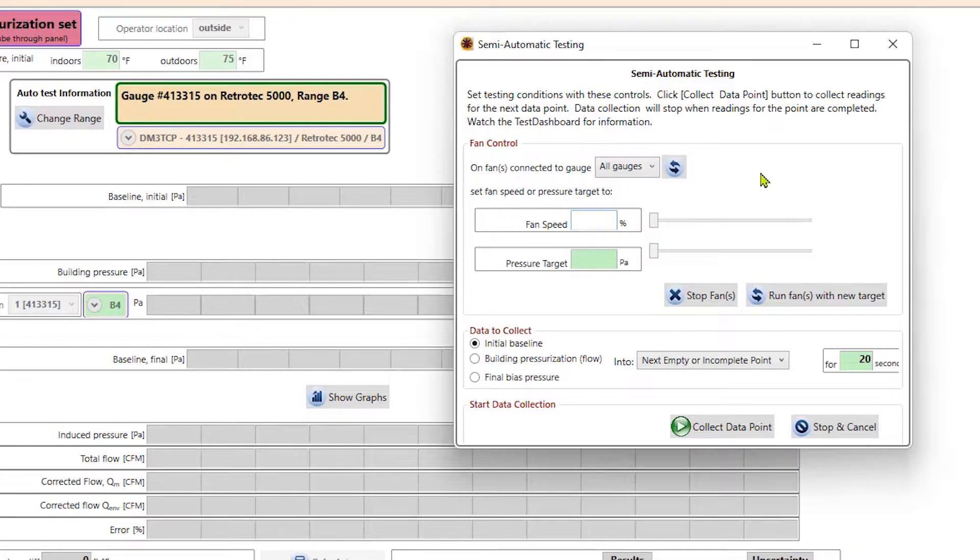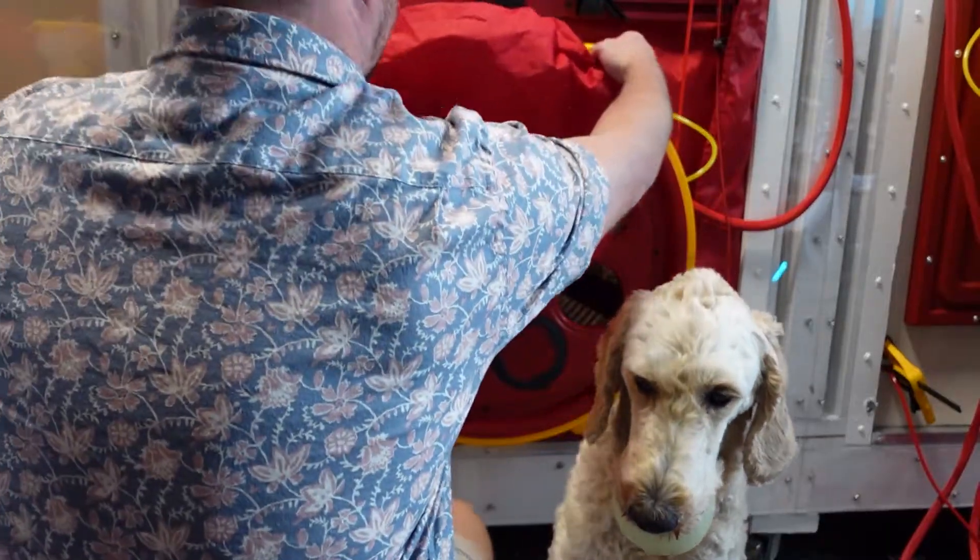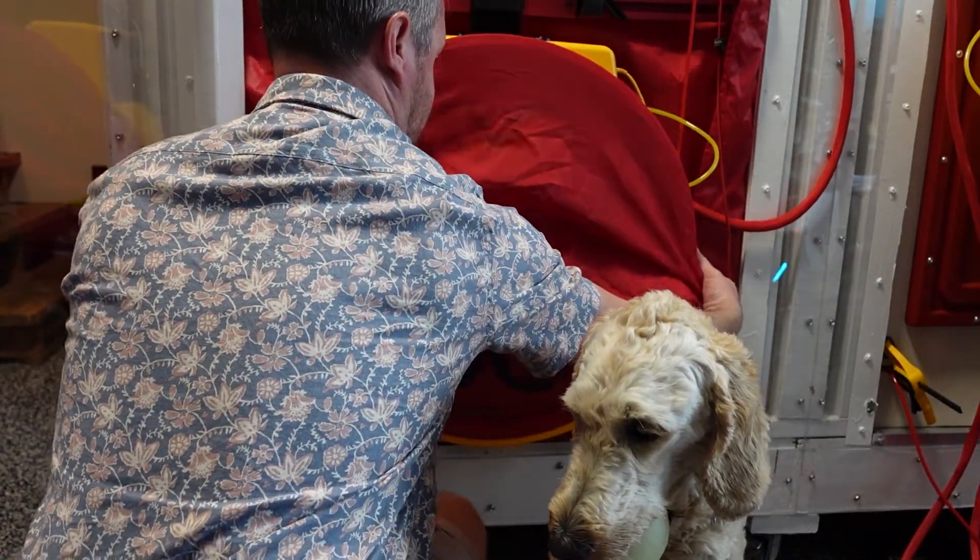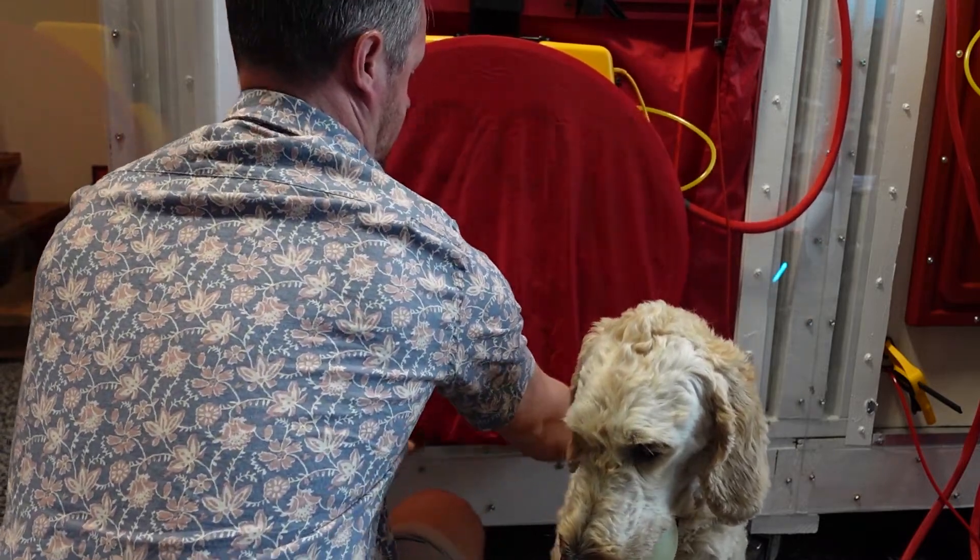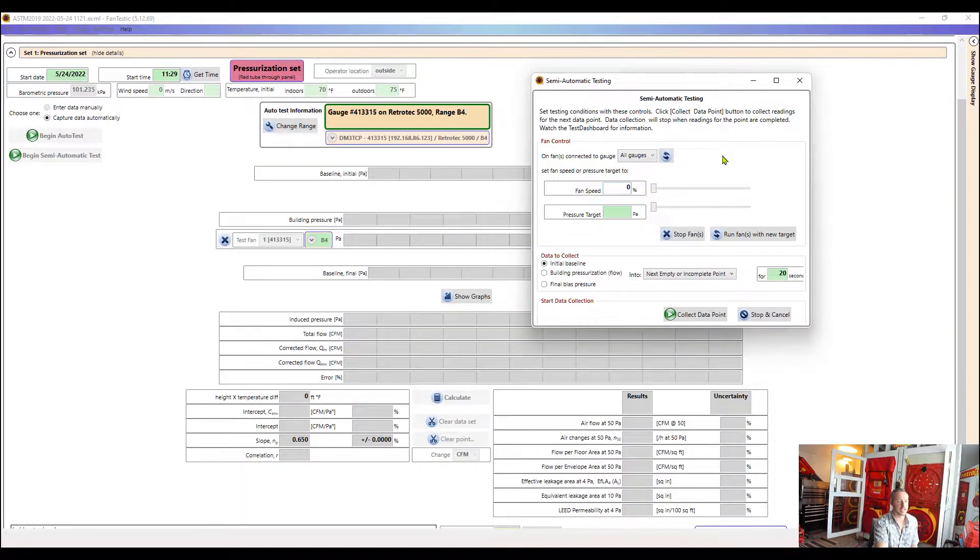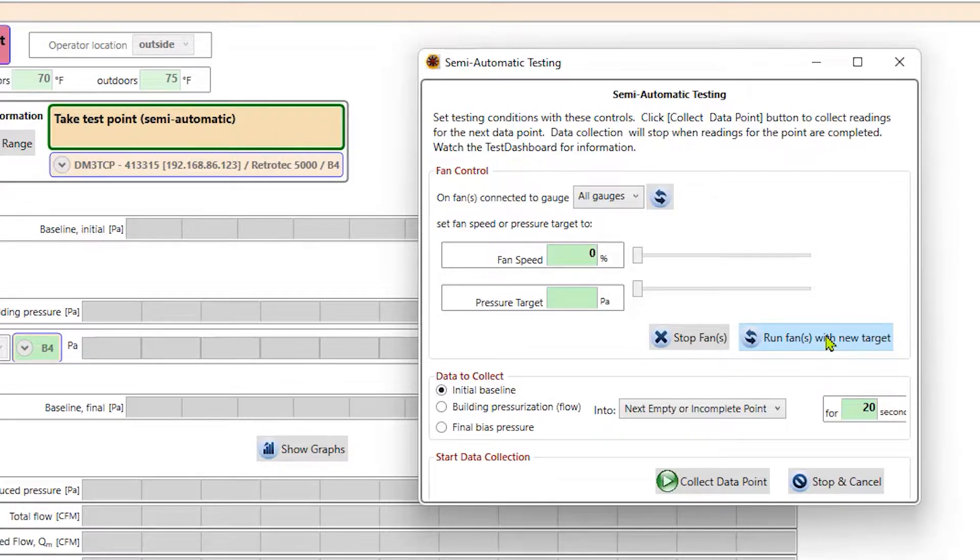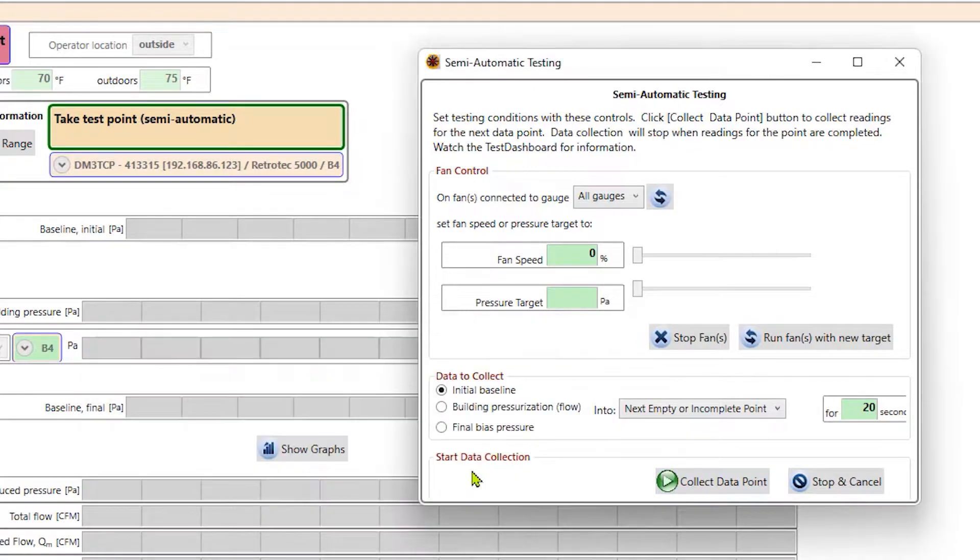And then I want to tell the fan speed to run at 0%. We're not going to run the fans any power. We're just going to log outdoor conditions. And before I do that, I want to cover up that fan. So either use the shower cap cover or put all the range plugs in. Now that the fan is covered up, I can just tell it to run fans. And now I can go ahead and collect data.